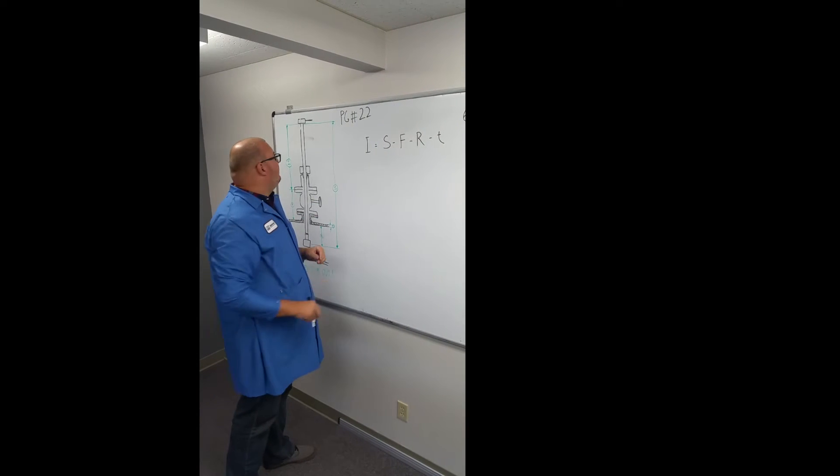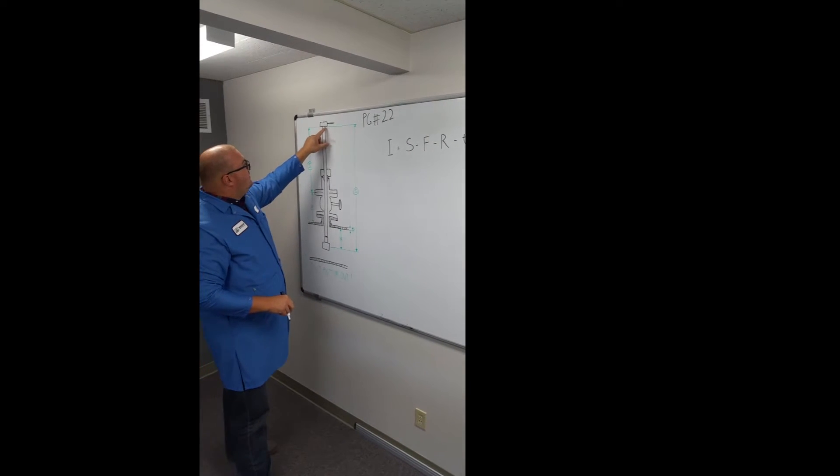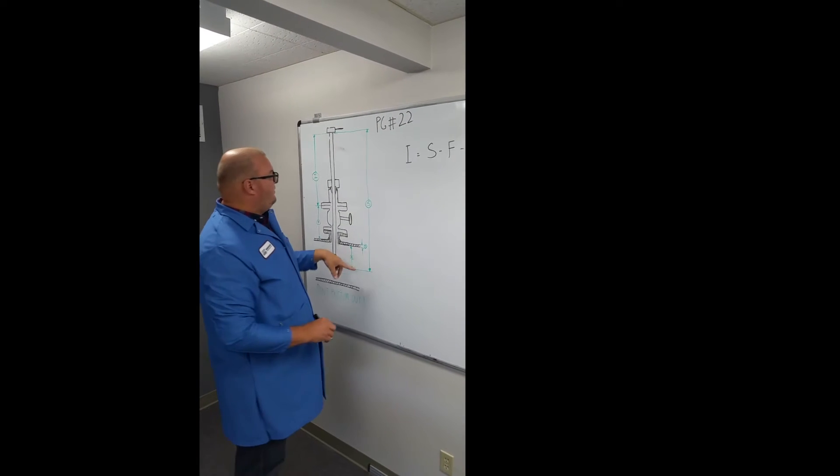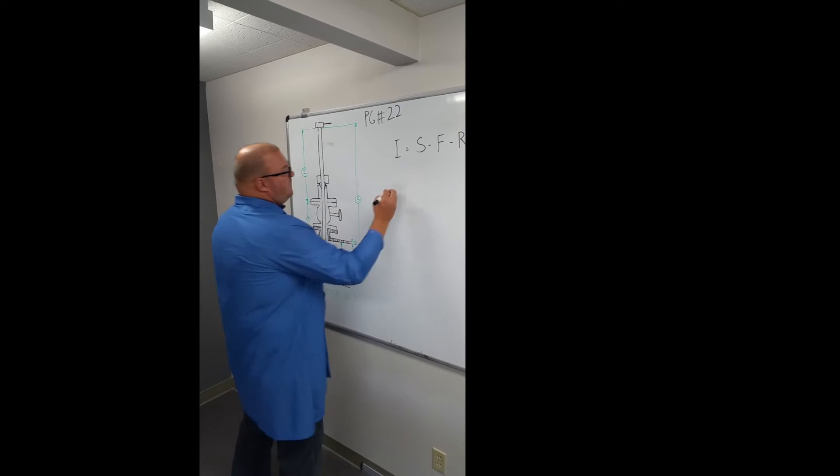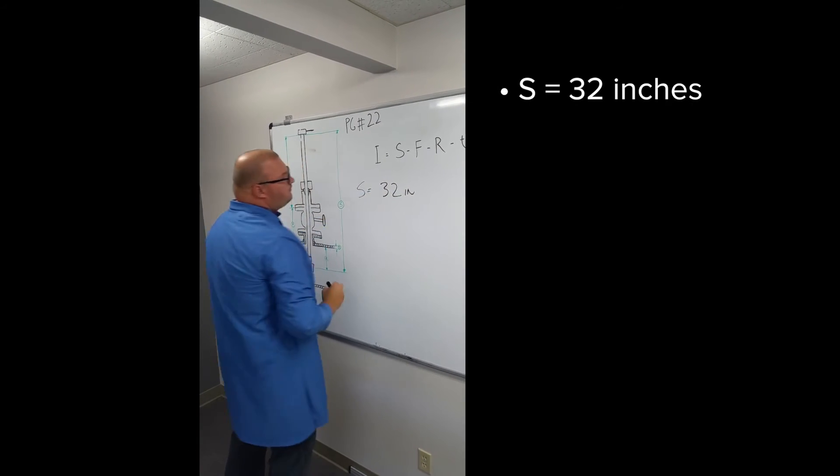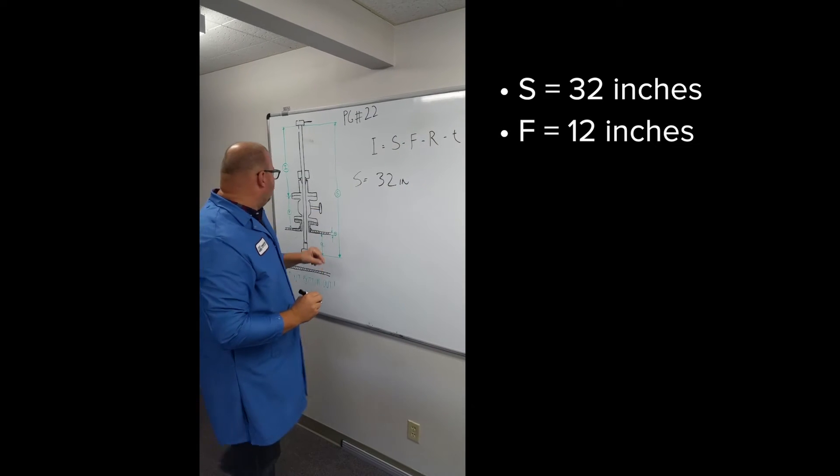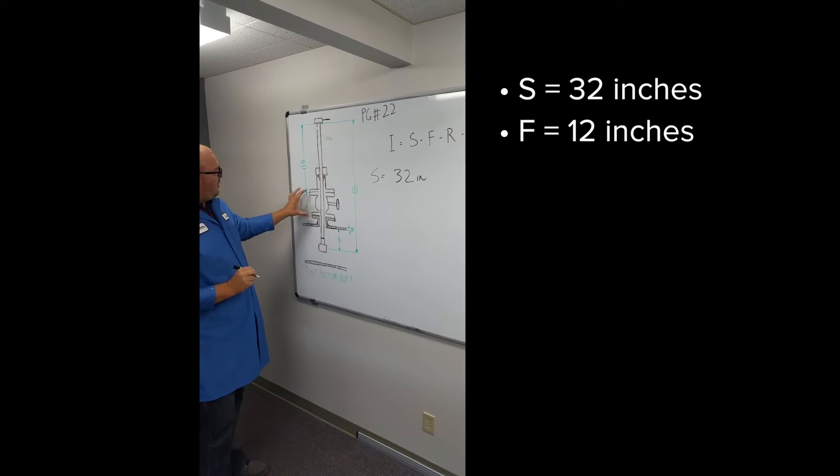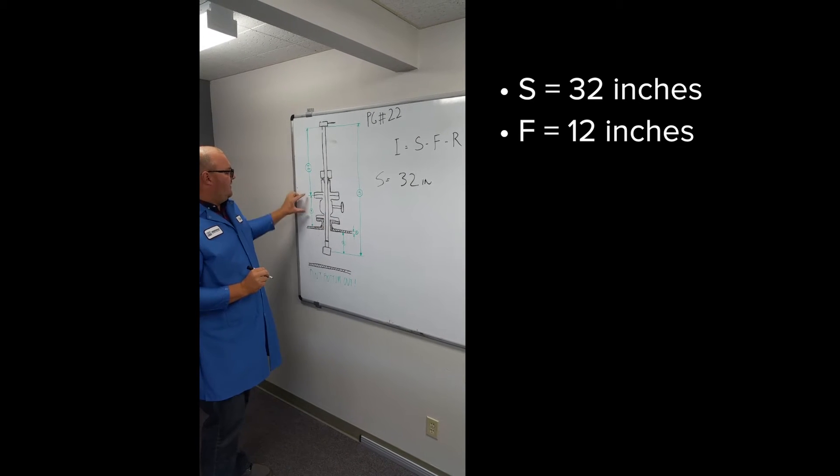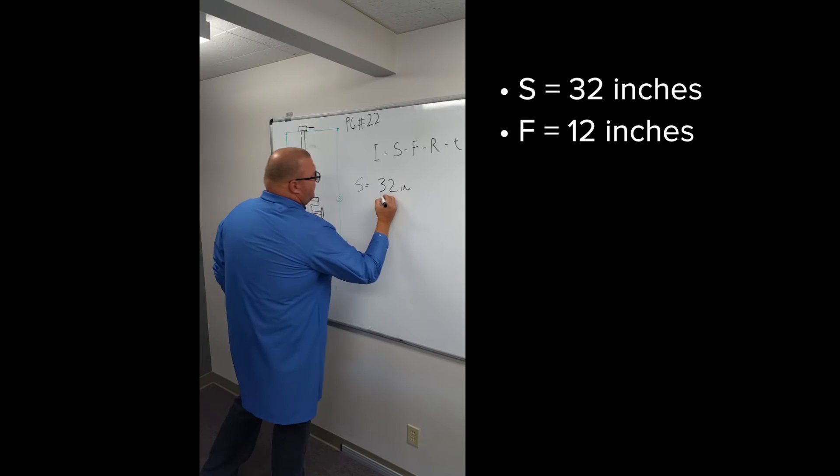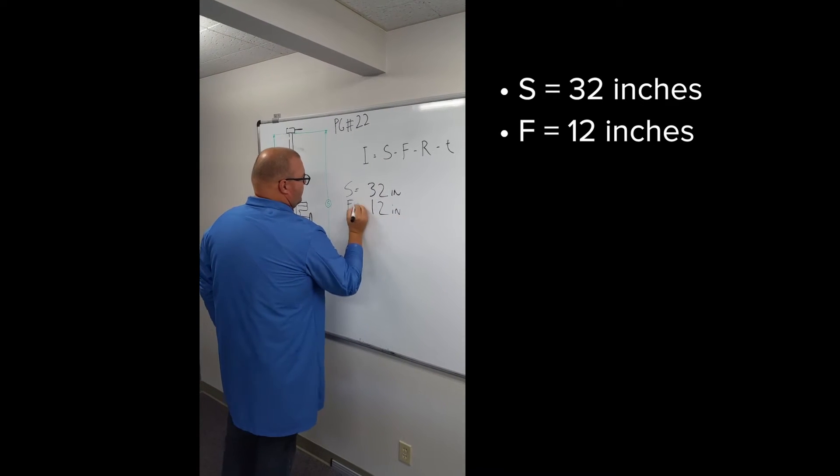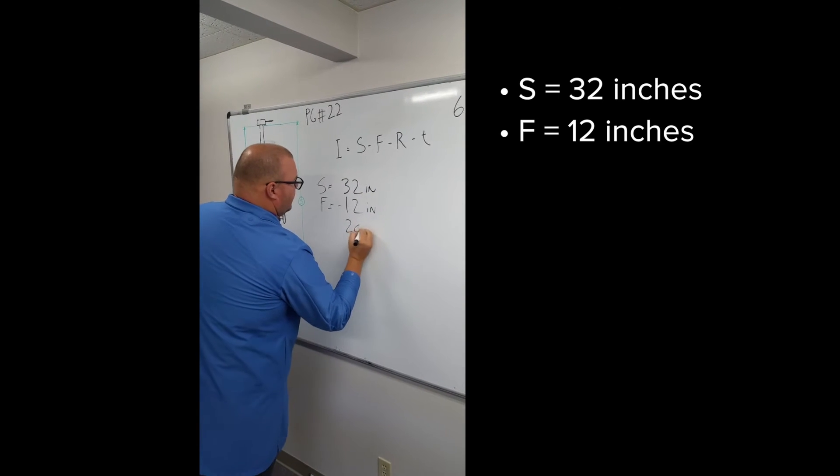S is our stem length of the probe which is the length from the pointer to the center of the head of the probe down here. On a standard length probe that's going to be 32 inches. Next is F which is the length of your process connection. In this case it's a flange weldlet and an isolation valve. F is 12 inches. If I subtract those, it's pretty easy, 20 inches.